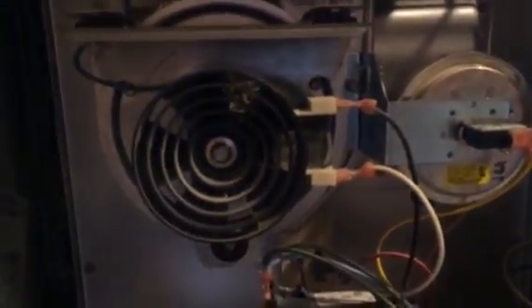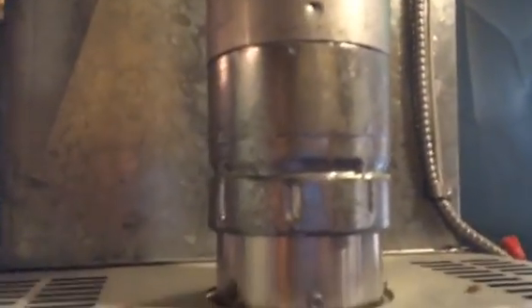This motor basically pulls heat from the burners down below, heat and products of combustion, through the heat exchanger, and basically introduces it to the flue, whereby heat from the flue rises up and into the vent, and heat basically carries it away. Buoyancy. Hot air, hot gases are buoyant and will then be carried out to the vent and outdoors.